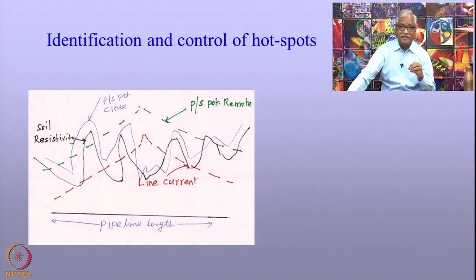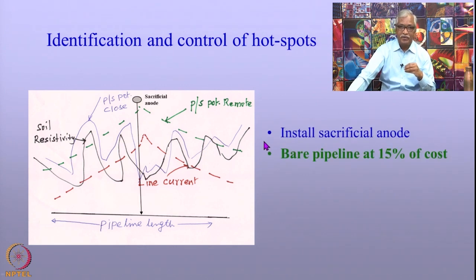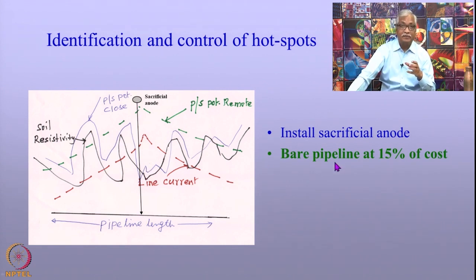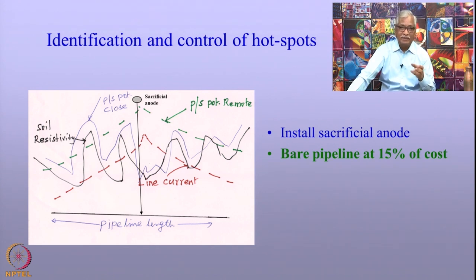The advantage of this technique is that since these structures are buried, all measurements are made above the ground. To control the corrosion at the hot spot, one way is to install a sacrificial anode at that location and make an electrical connection to the pipeline. With this, it is possible to protect the pipeline from severe corrosion by spending only about 15 percent of the overall cost of cathodic protection of the pipeline — that is the real advantage of using multiple surveys.